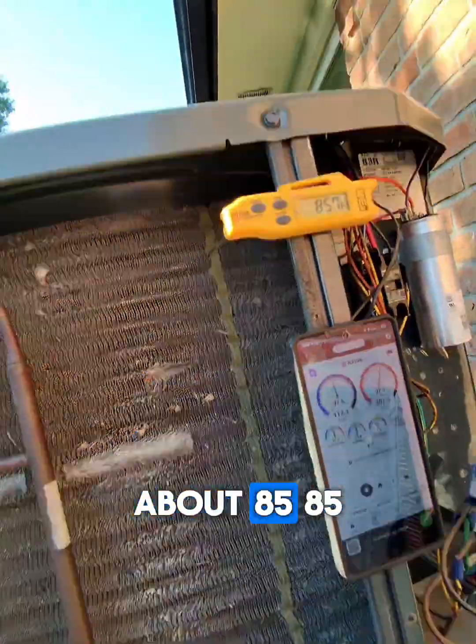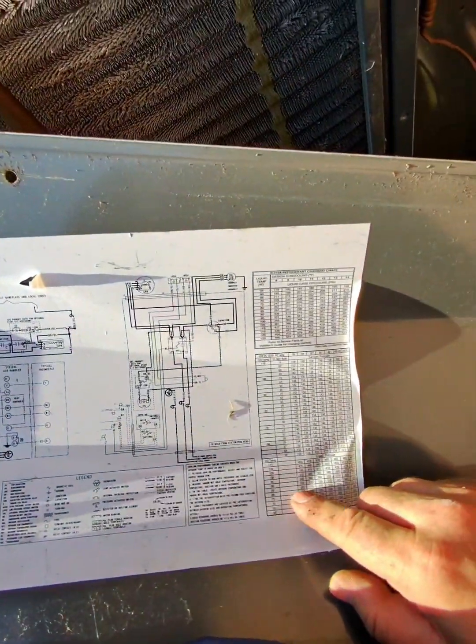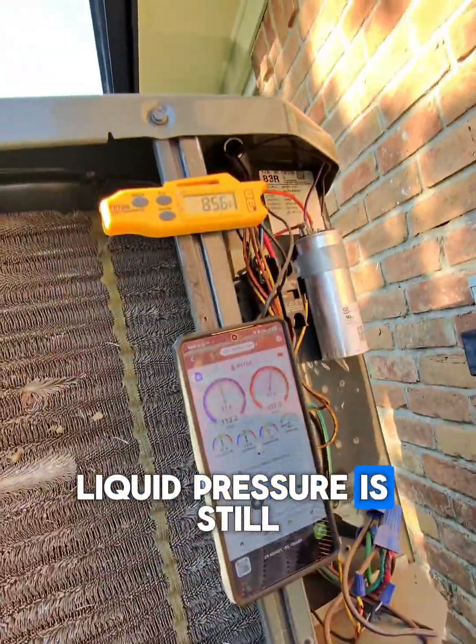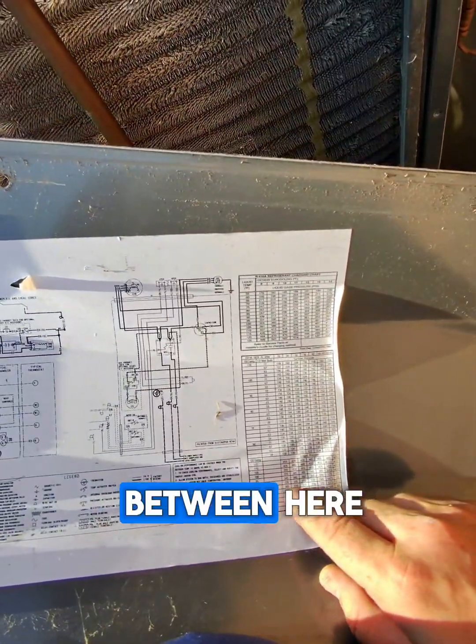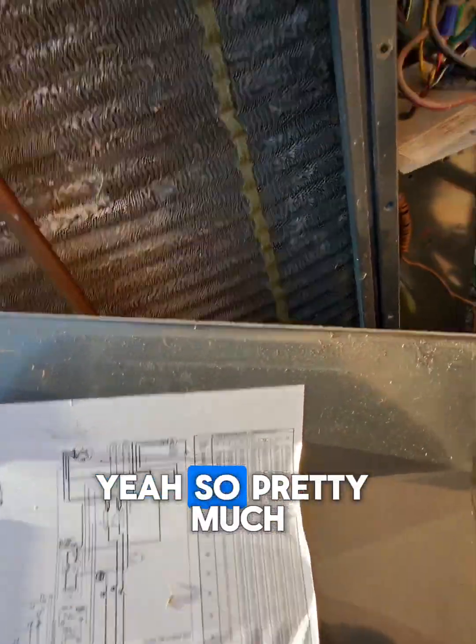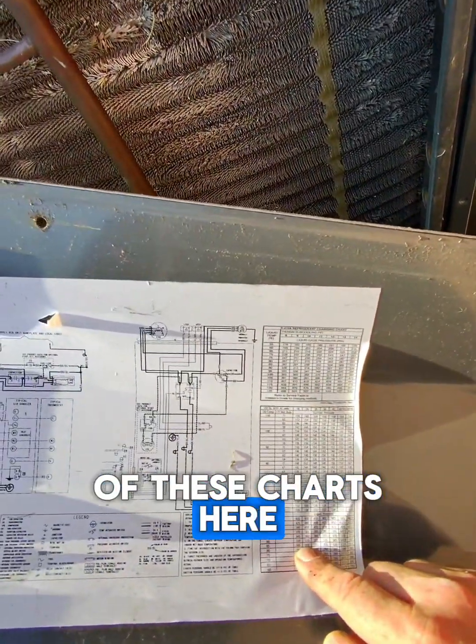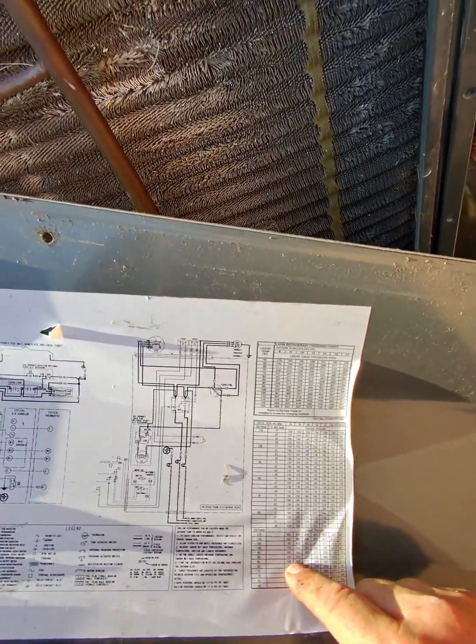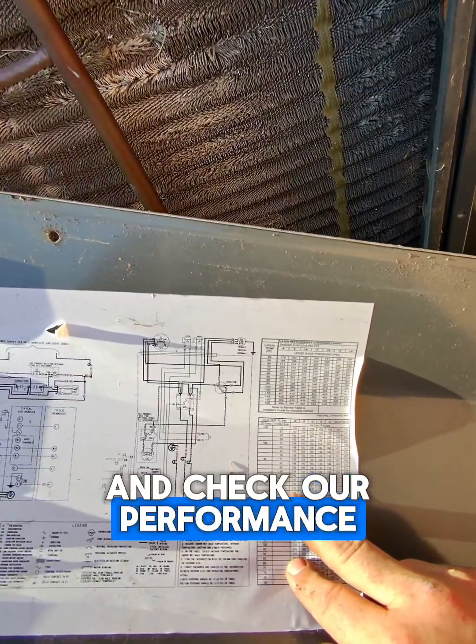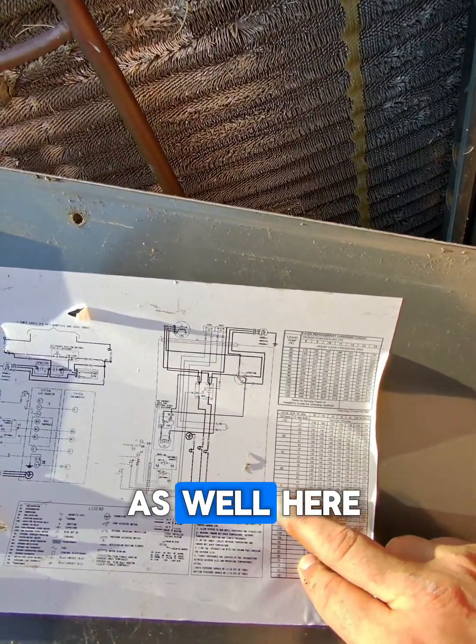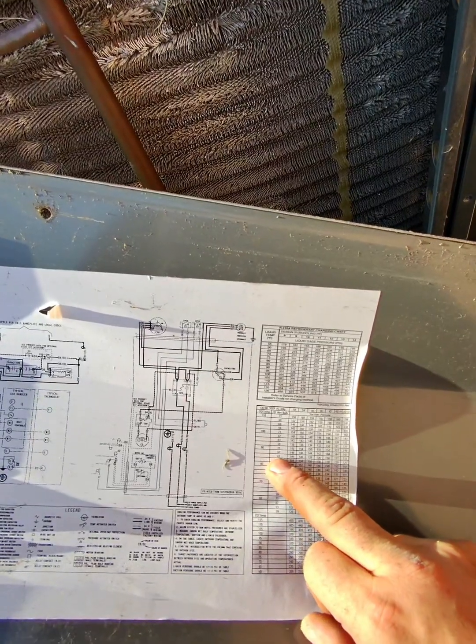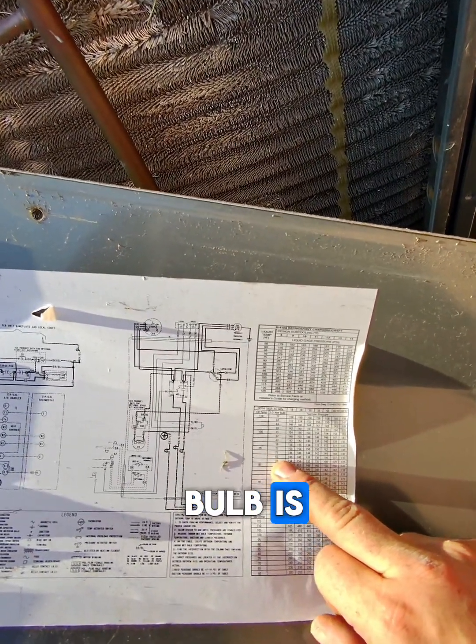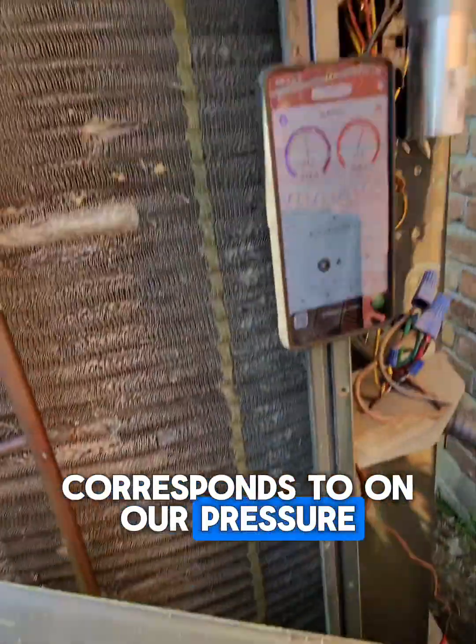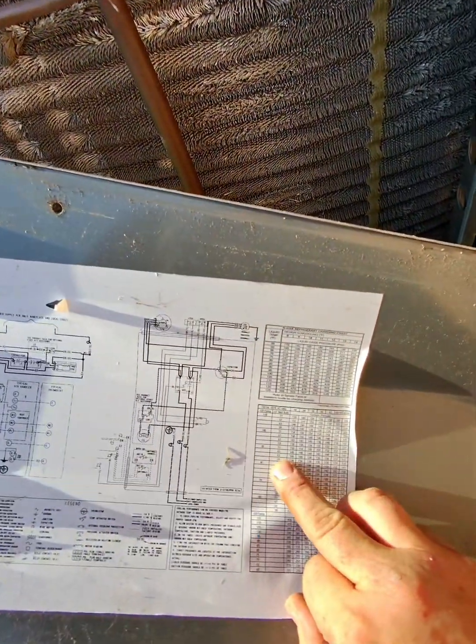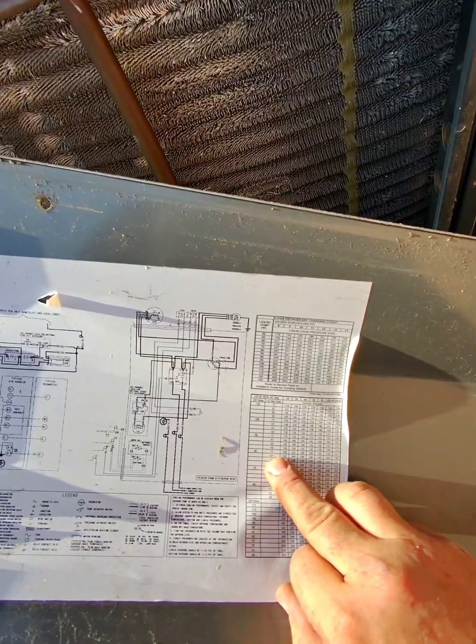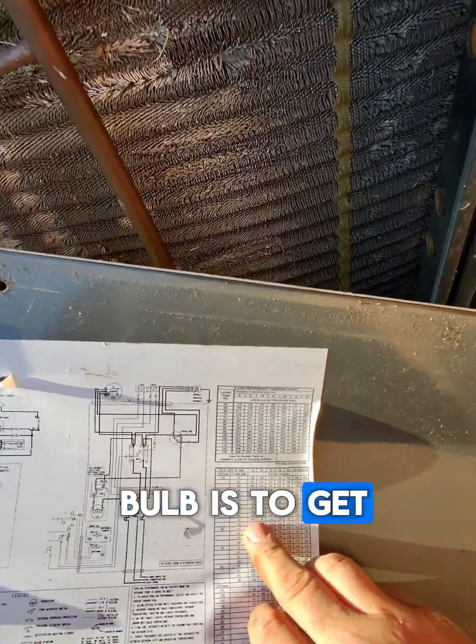Outdoor temp, yeah, about 85, 85. Liquid pressure is still about 307 through 10 in between here. Yeah, so pretty much on point on each of these charts here. Let me go ahead and check our performance as well. Okay, we're going to be about 85. See what our wet bulb is. And see what that corresponds to on our pressure. Pressure is running about 110. Check what our wet bulb is to get that cross reference there.